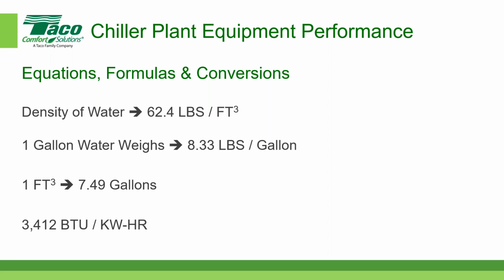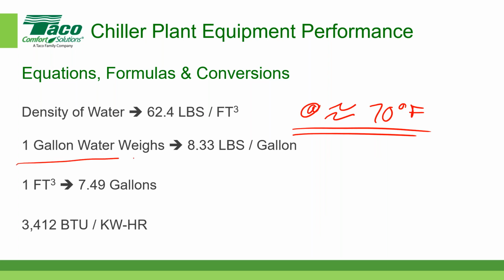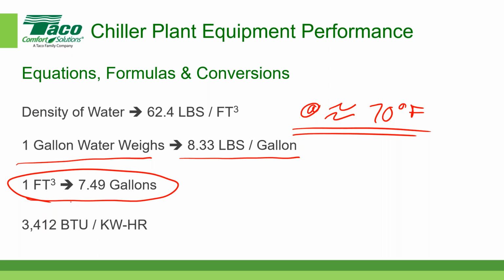The density of water is approximately 62.4 pounds per cubic foot. The reason I put that up there is because it's a good number to put in your basket of easy to remember things. And again, that's clear water. There's nothing in the water. It's not salt water. It's not water and glycol. It's just clear water at approximately 70 degrees Fahrenheit, give or take a little bit. And that's the density of water. And 1 gallon of water weighs about 8.33 pounds. Another good number to remember is that a cubic foot of water is about 7.5 gallons.